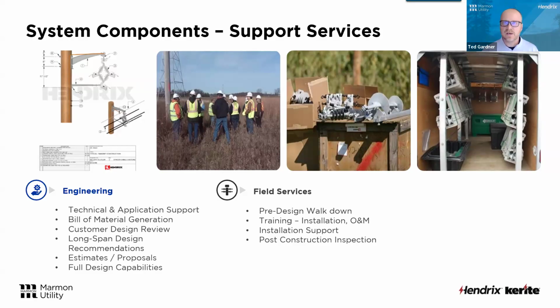So I would encourage anybody that has some of the existing spacer cable system and they have a lot of questions, set up some training for us to come out. And those guys will come in and do our O&M training. We make the assumption that you've already got spacer cable on your system, and you just need to know how to splice it, how to ground it. If you've got a tree laying on the line, what's the safest way to remove it? You get a broken bracket or a broken phase conductor, how to fix it, broken pole, the best way to attack that.